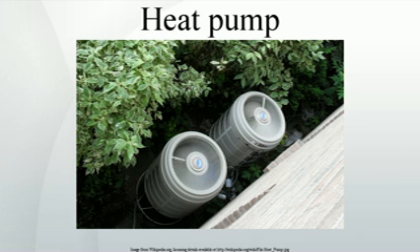On the other hand, ground source heat pumps, GSHP, benefit from the moderated temperature underground, as the ground acts naturally as a store of thermal energy. Their year-round COP is therefore normally in the range of 2.5 to 5.0. When there is a high temperature differential on a cold day, for example, when an air source heat pump is used to heat a house on a cold winter day of 0 °C, 32 °F, it takes more work to move the same amount of heat to indoors than on a mild day.